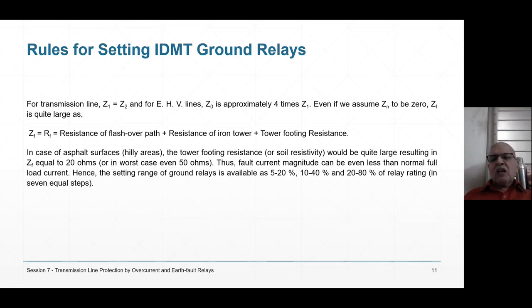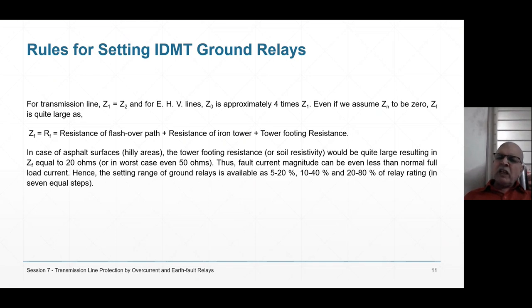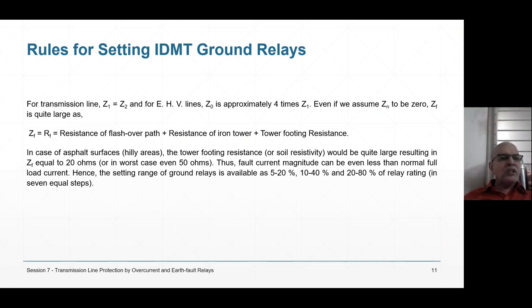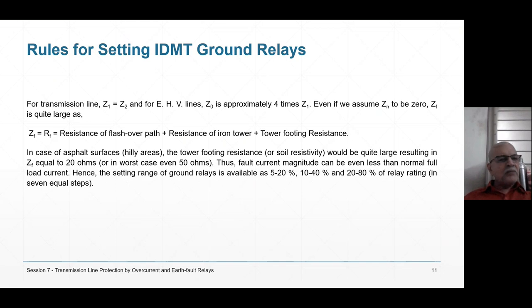In older electromagnetic versions, three sensitivity ranges were available: 5–20% in seven equal steps (5, 7.5, 10, 12.5, 15, 17.5, 20), also 10–40% and 20–80%. In numerical relays, the range is now 1–20% or 1–40% in steps of 1%, so setting is straightforward. These are all important concepts: how to set the relays is required in numerical relays just as before — concepts are permanent even as the methodology changes.